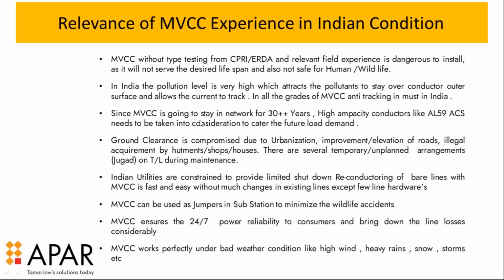And since the MVCC is going to stay in the network for 30-plus years, while considering the covered conductor you should also see that in the future the line loads will increase. So you should choose the conductor in such a way that it can take the future load requirements also. Rather than replacing it after 10-15 years, it should be able to serve you for 30 to 40 years.